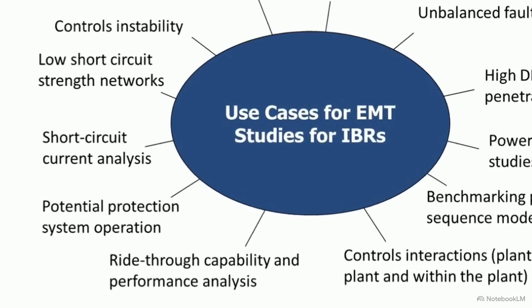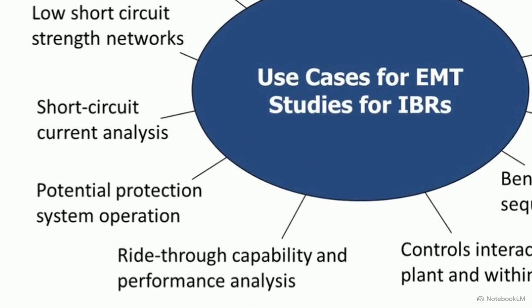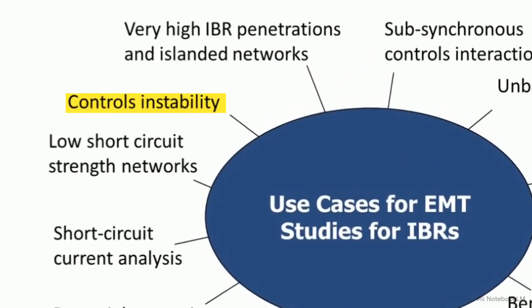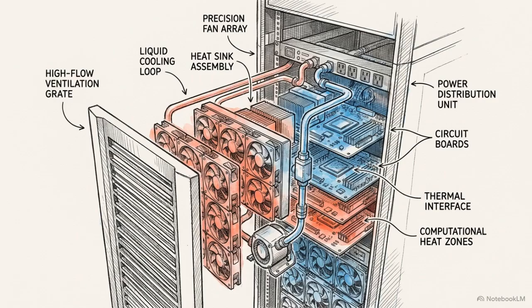By acting as an ultra-high-speed camera for the grid, EMT allows engineers to accurately test complex inverter ride-through capabilities and pinpoint control instabilities before they ever touch real equipment. But closing the resolution gap comes at an extreme operational cost. EMT simulations require massive computational horsepower, taking hours or days to calculate what a legacy simulation solves in seconds.